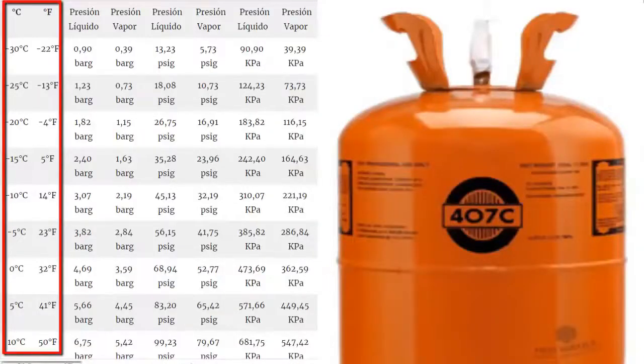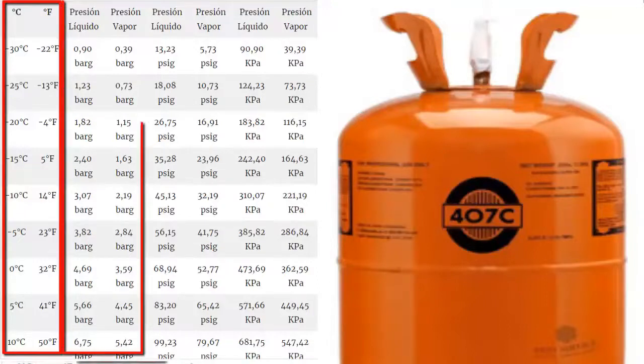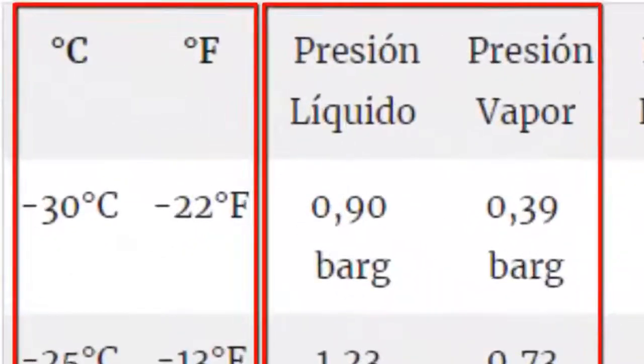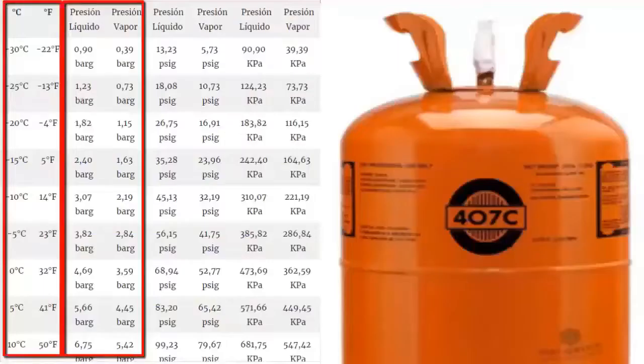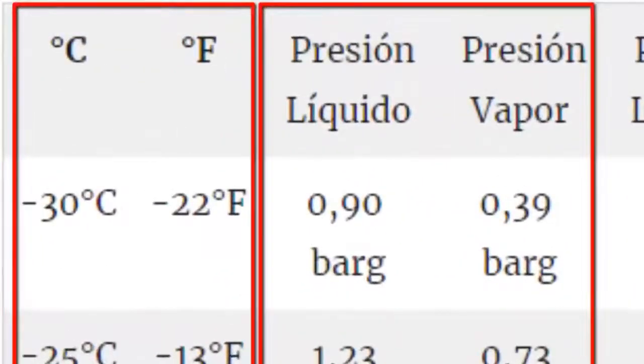On the left in the first column, we have the saturation temperature. In the next two columns, we have the bubble or liquid pressure, and then the vapor or dew pressure. You may wonder why there are two types of pressures — this is because the gas has a temperature glide. This sliding means that the temperature of its transformation from liquid to vapor, or from vapor to liquid, does not remain constant. In a zeotropic mixture, the change of state of the most volatile compounds occurs first, causing the temperature to increase throughout the phase change until evaporation occurs in its entirety.